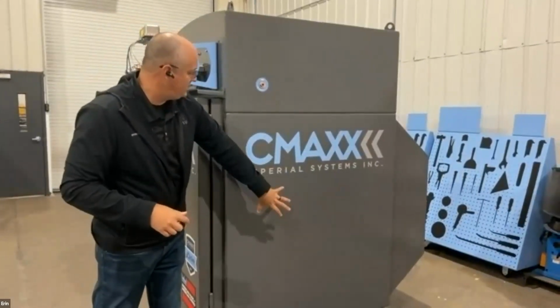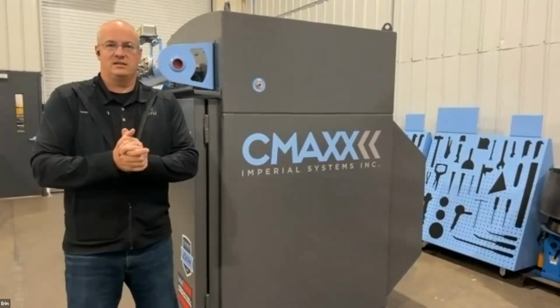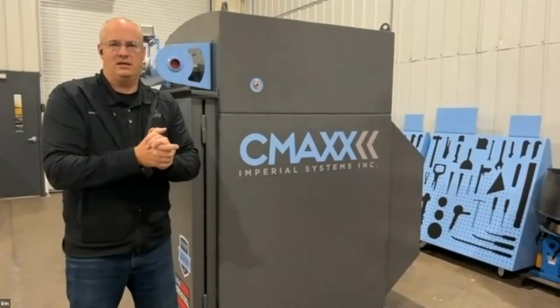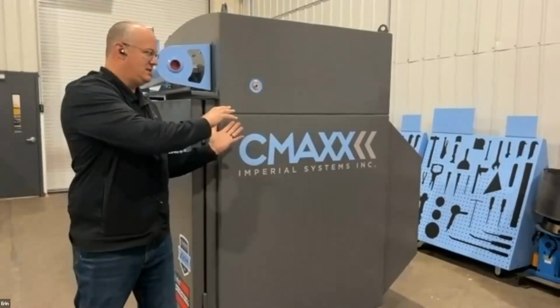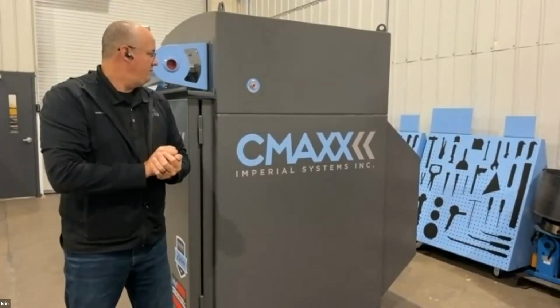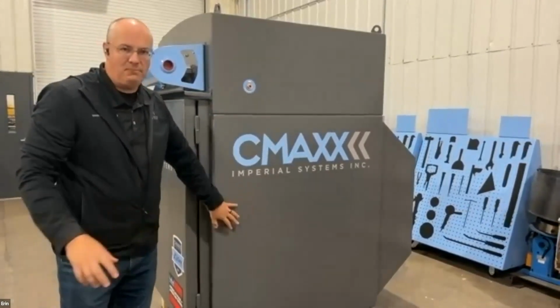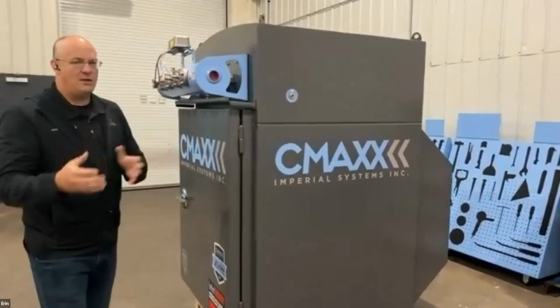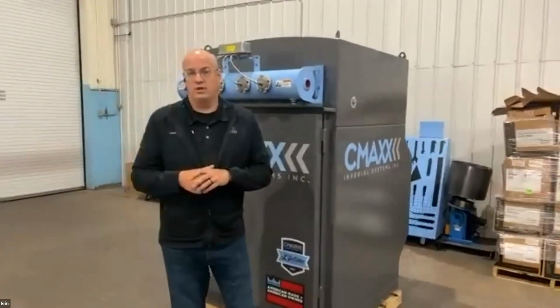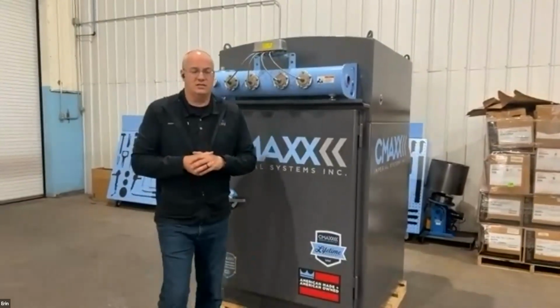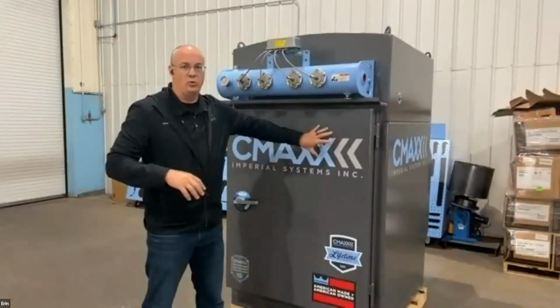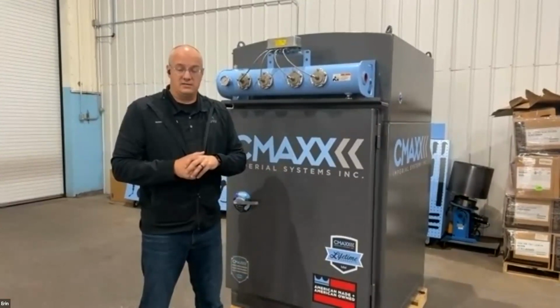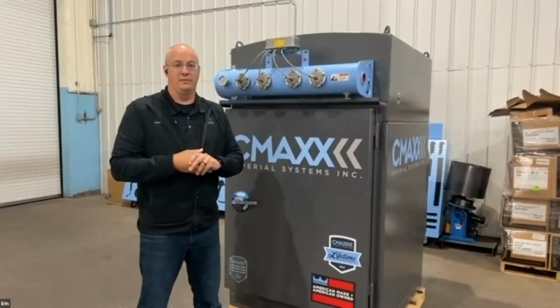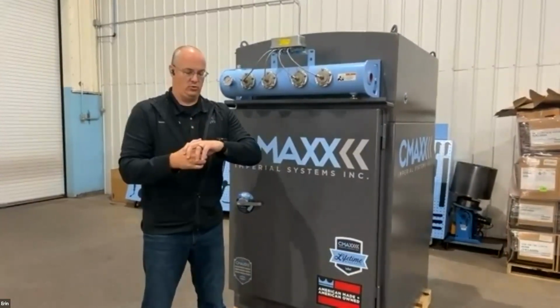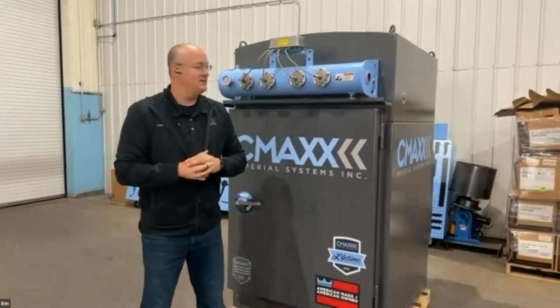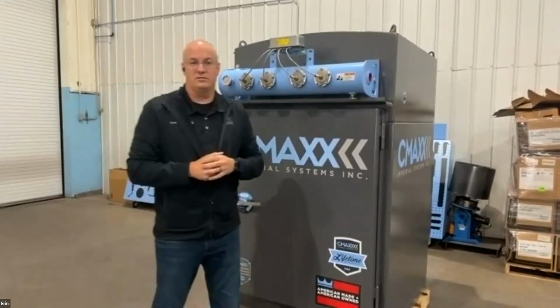So when you put the explosion panel on here, what it does is taking what Dave said is kind of a bomb, and we're making it into more of a directional device. So it's making it maybe a little bit more into a gun. And we're going to take that danger and we're going to aim it in a safe direction. So that's really it. They're not overly complicated machines with how they work. What gets complicated is knowing how to size them properly to make sure that all your safety features are in place and that everything is installed correctly and put in place. When they're done correctly, they work great and you forget about them. When they are not done correctly, it can be a potential risk or hazard to those that are around them. And that's really what we're just hoping to help you guys understand more of here. I might have went a little quicker than Dave was anticipating, but I'm glad to leave a little bit of extra time for questions if we have those.